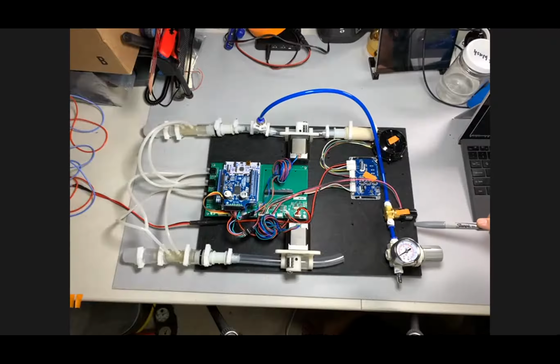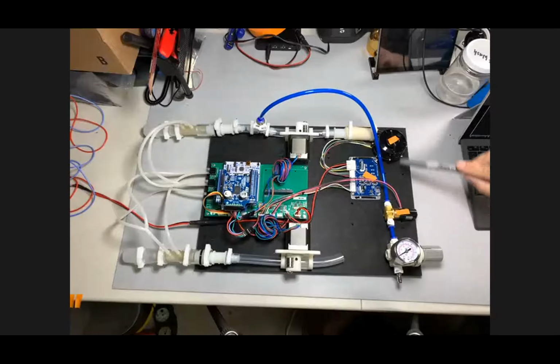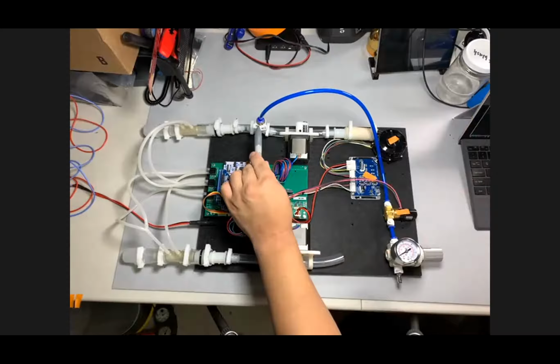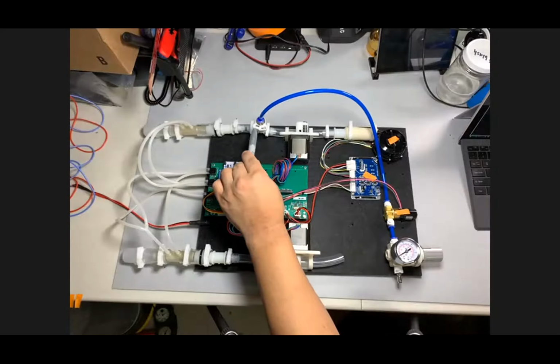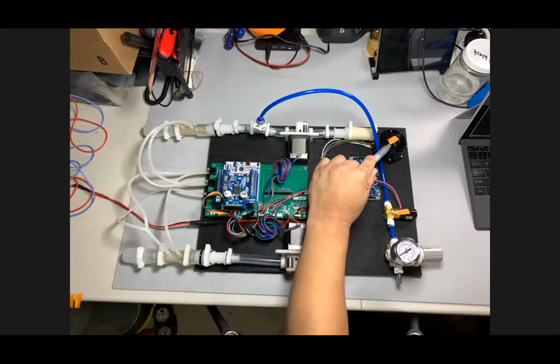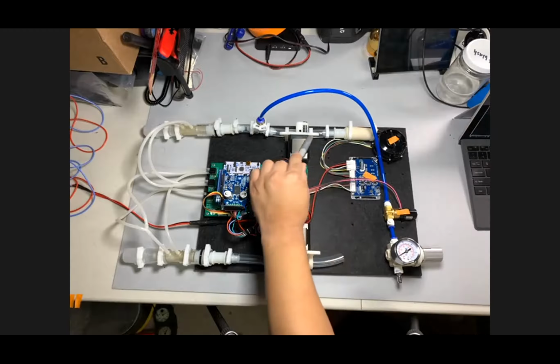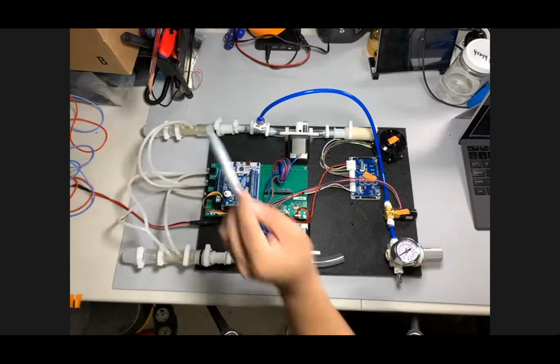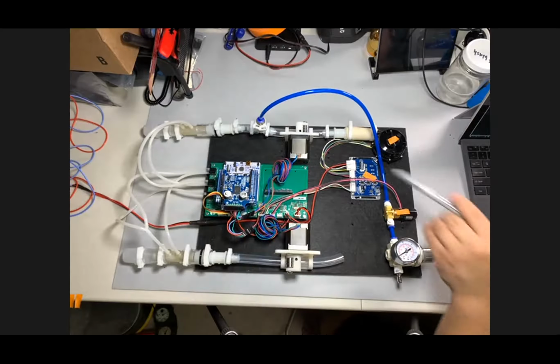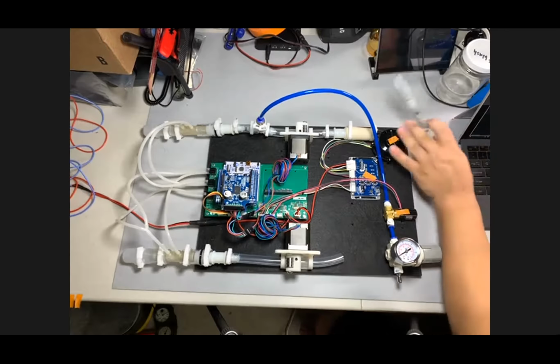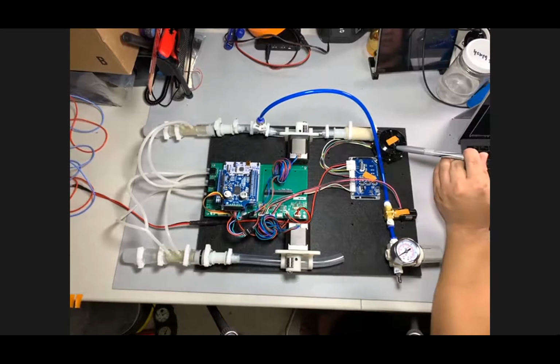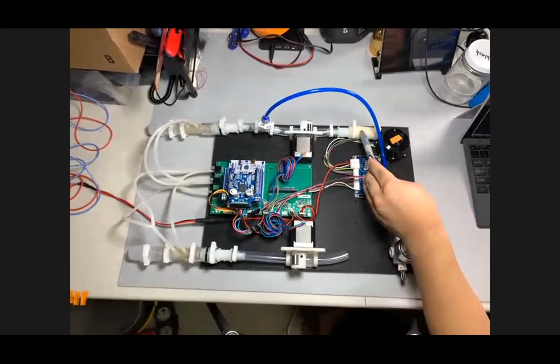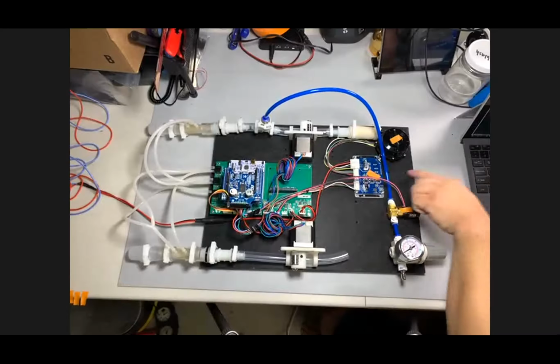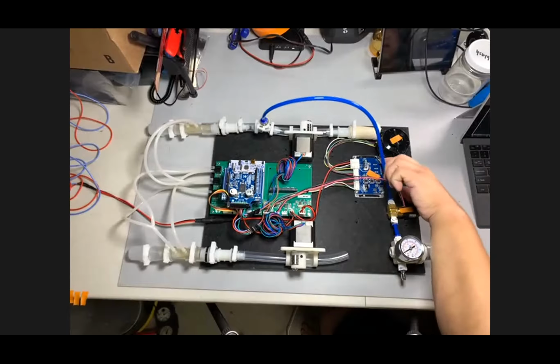Okay, so oxygen comes in here. It feeds into a mixing branch right here, where it joins the feed pathway from the ambient air and then goes out to the rest of the ventilator. So we've got more parts here in the upstream. So let's actually start here from the blower. The blower outputs to this 3/4 tubing, which is kind of what we've standardized as our general internal tubing, unless otherwise needed.